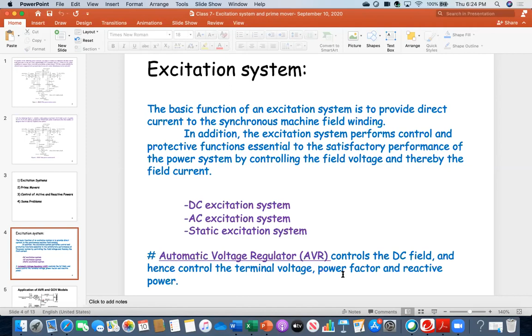Okay, and now it has that excitation system. Now it has some sort of controller, which is called the AVR, automatic voltage regulator. What it does is control the DC field, and hence control the terminal voltage, power factor, and reactive power. So the function of the AVR, or automatic voltage regulator system, is to control the DC field and, accordingly, the terminal voltage, power factor, and reactive power.